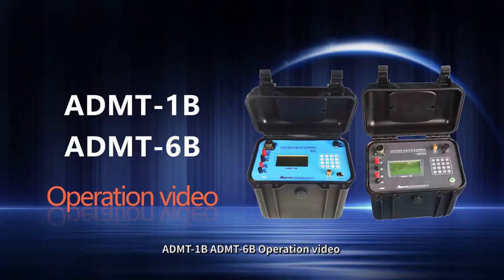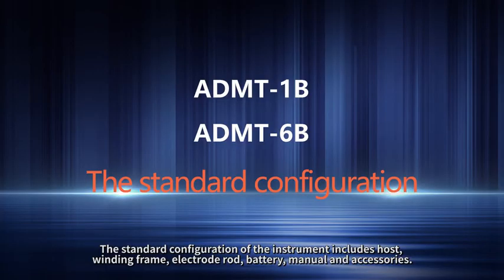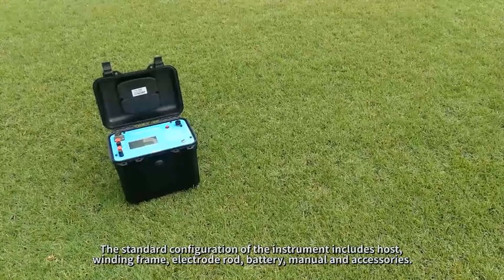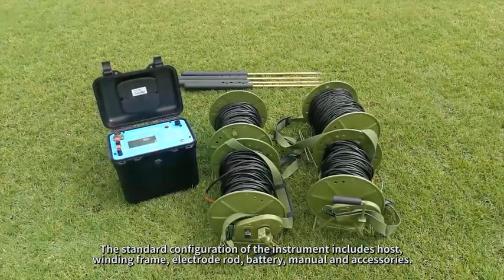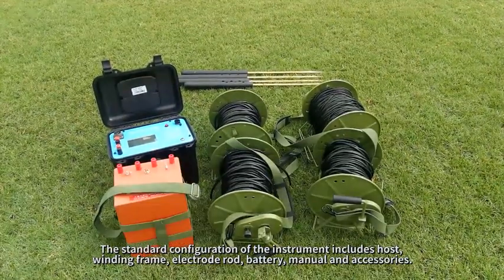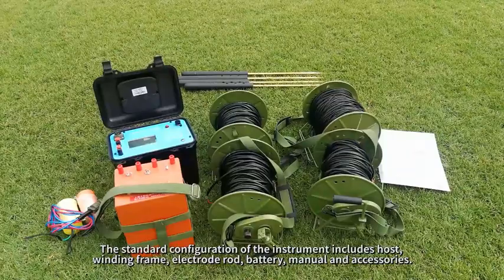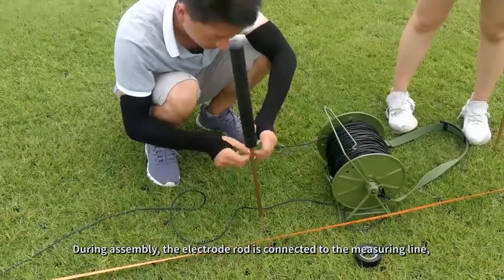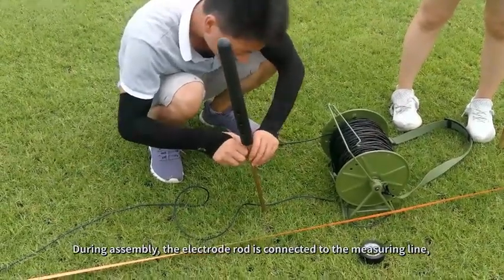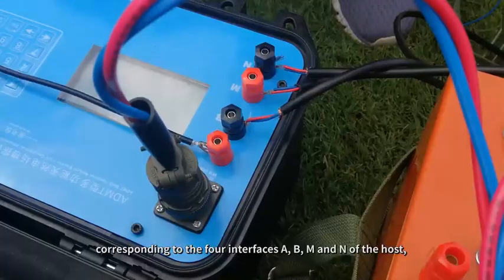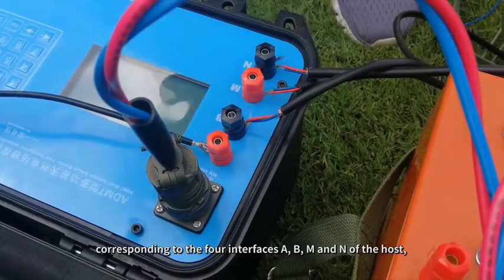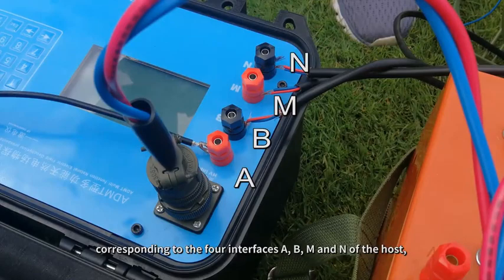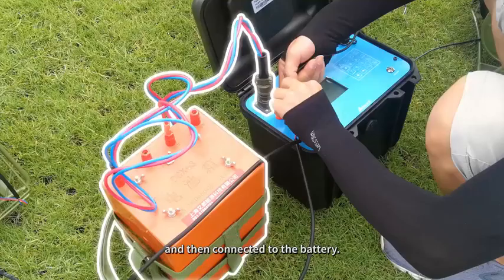ADMT1B, ADMT6B operation video. The standard configuration of the instrument includes host, winding frame, electrode rod, battery, manual and accessories. During assembly, the electrode rod is connected to the measuring line, corresponding to the four interfaces A, B, M and N of the host, and then connected to the battery.